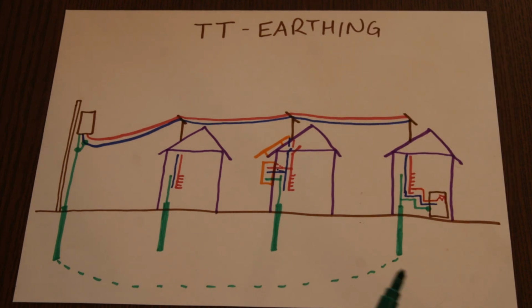And so if we switch from one power source to the other, we also have to take care of that situation. If the inverter takes over into a sort of off-grid setup, then we need to bond ground and neutral, so that at the end everything works exactly similar in our distribution as it would when the power comes from the grid. So all the RCDs have to work the same way, and also our line breakers should work exactly the same way as they would when the power comes from the grid.